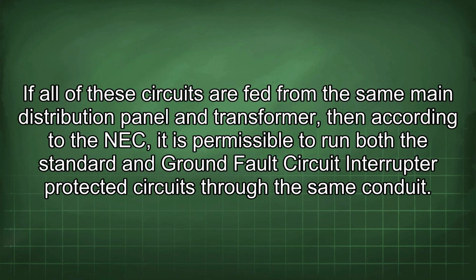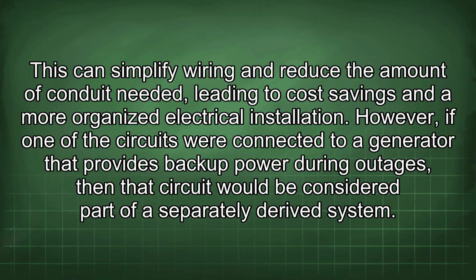If all of these circuits are fed from the same main distribution panel and transformer, then according to the NEC, it is permissible to run both the standard and ground fault circuit interrupter protected circuits through the same conduit. This can simplify wiring and reduce the amount of conduit needed, leading to cost savings and a more organized electrical installation.